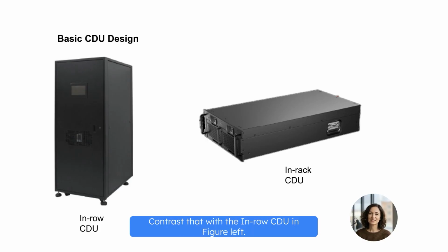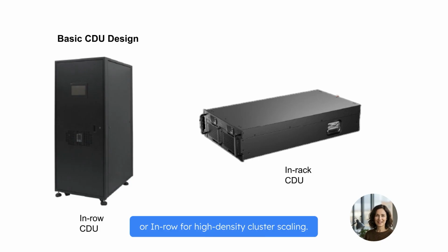Contrast that with the in-row CDU in figure left. This is a floor standing unit with much higher capacity. It doesn't serve just one rack. It drives the flow for an entire array of racks. It connects to a larger network of manifolds, supporting either top or bottom feed configurations. So the design choice is simple. Use in-rack for granular control, or in-row for high-density cluster scaling.